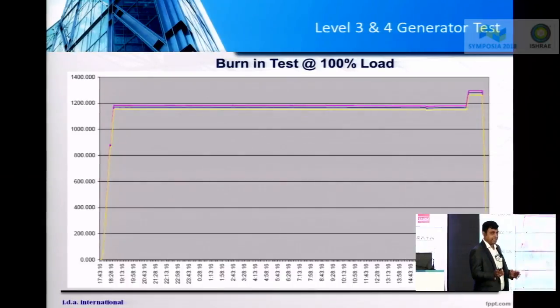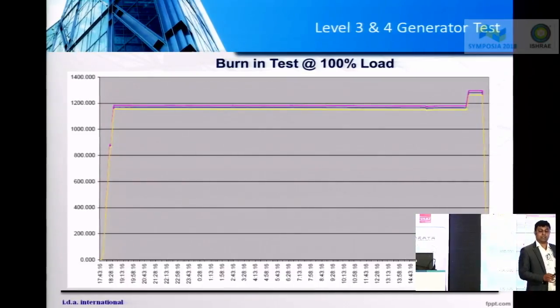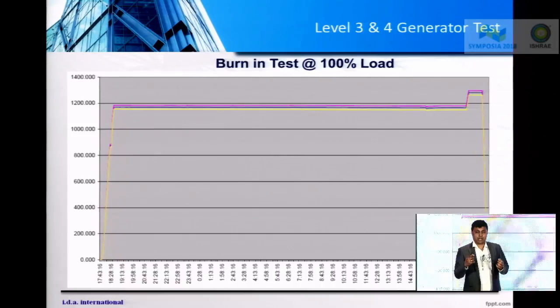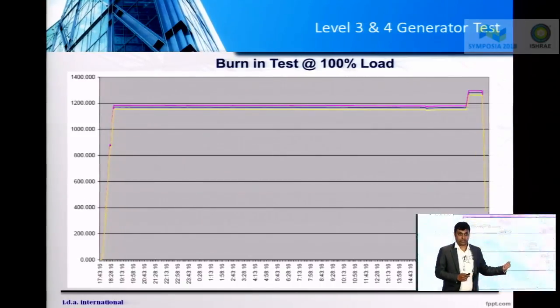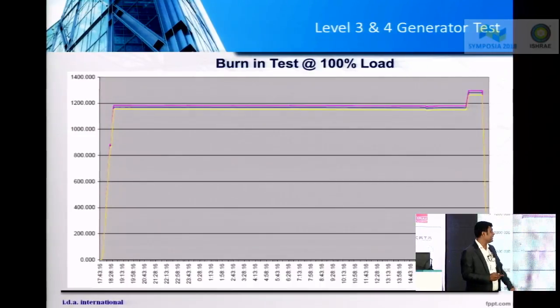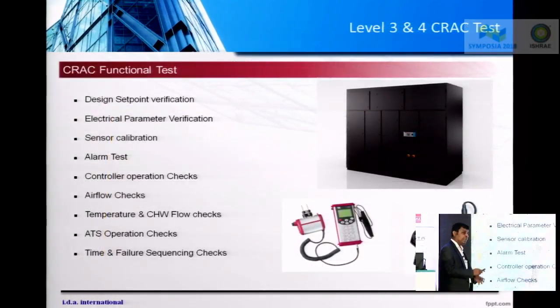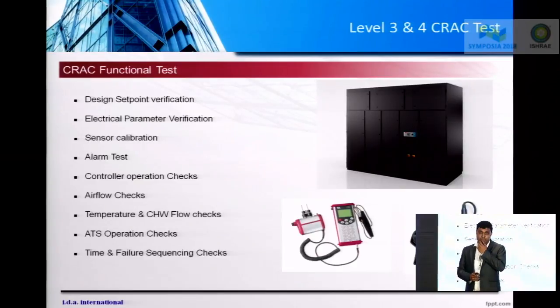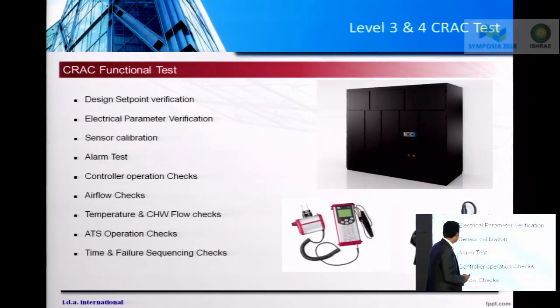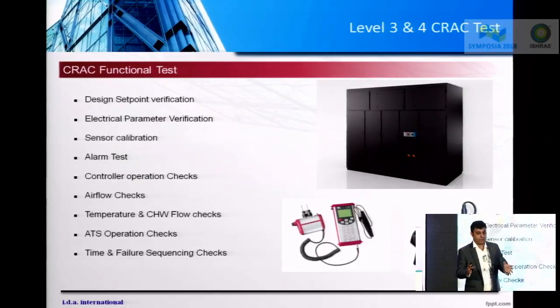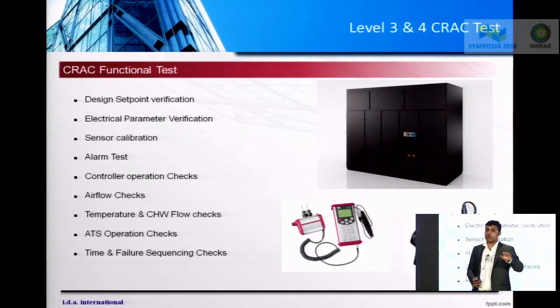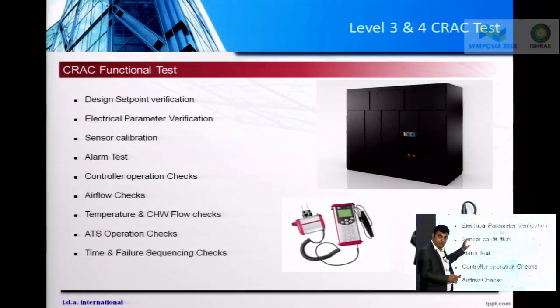Again, burn-in test, it is similar to UPS. Many failures, or some of the failures, could normally take place during this particular testing, which is burn-in test at full load condition. Let's come to precision air conditioning units, or we also call it CRAC units. So if I'm verifying the performance of a CRAC unit, I have to ensure that the following steps are verified.